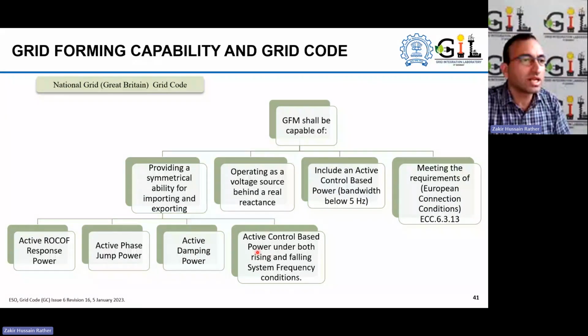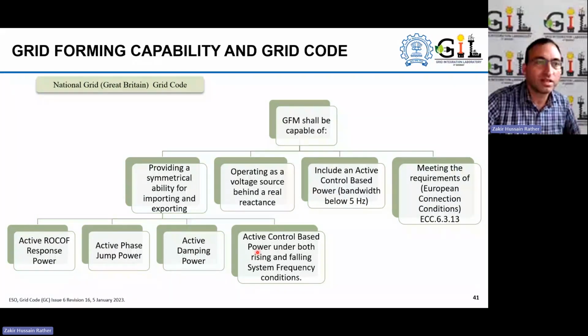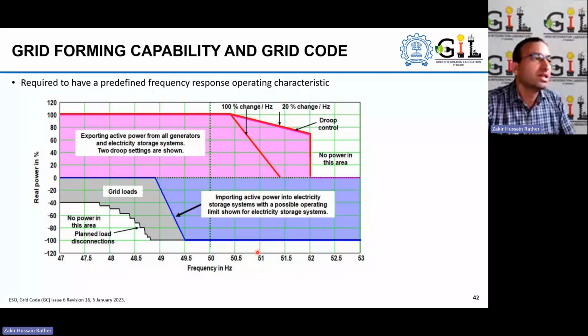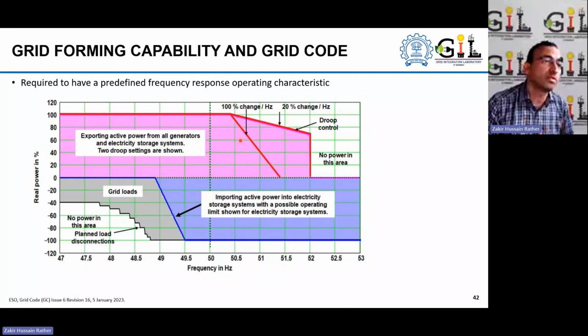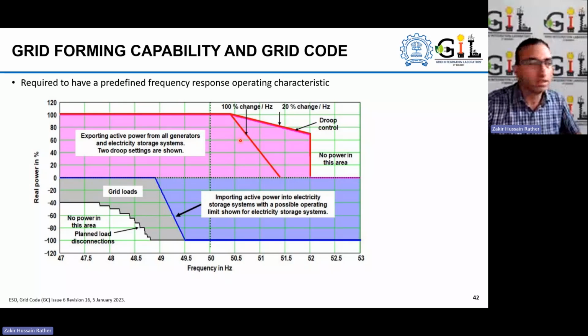Similarly, other requirements are relatively additional in grid forming technology. In this case, for the real power output, you can see a 100% change in power per hertz, which is quite a bit faster here. You can see the requirement in terms of these grid forming technologies.